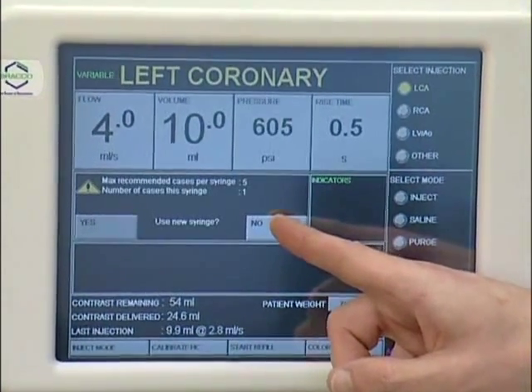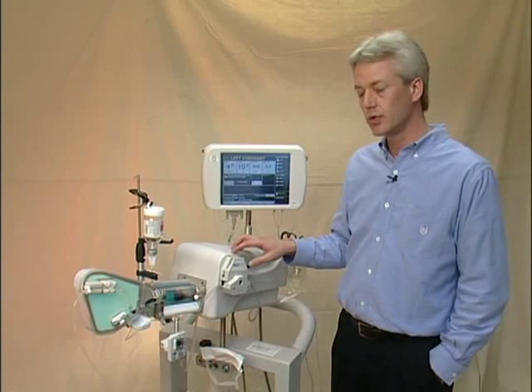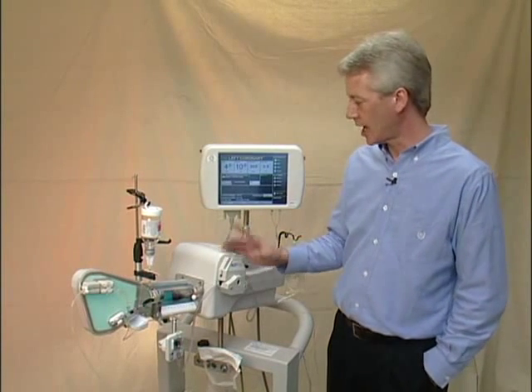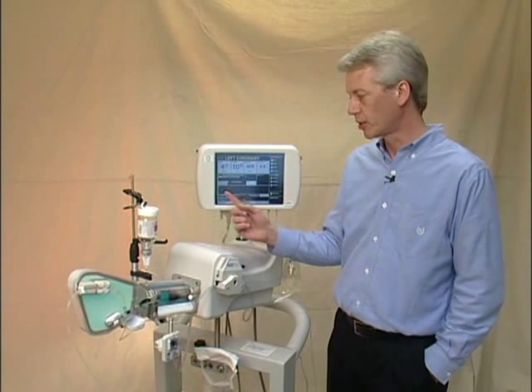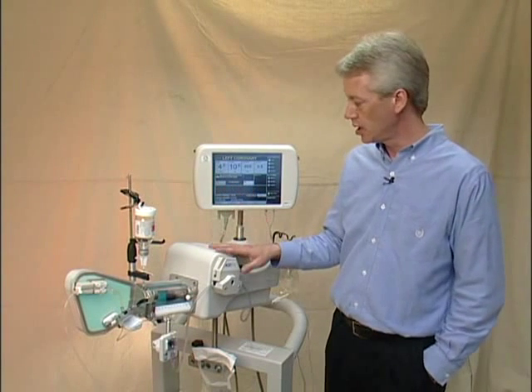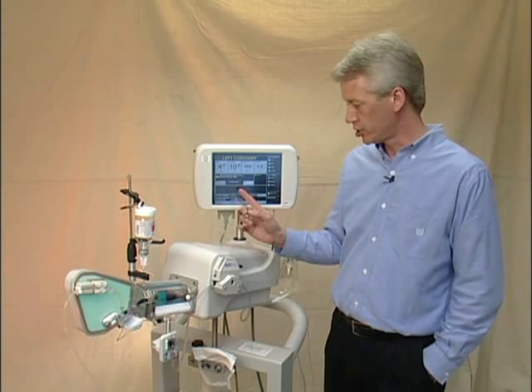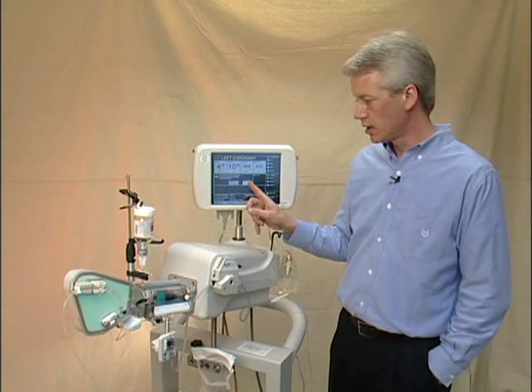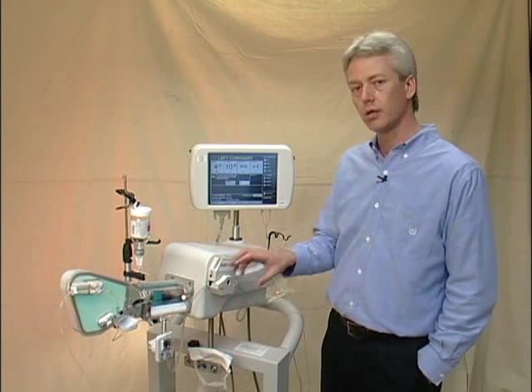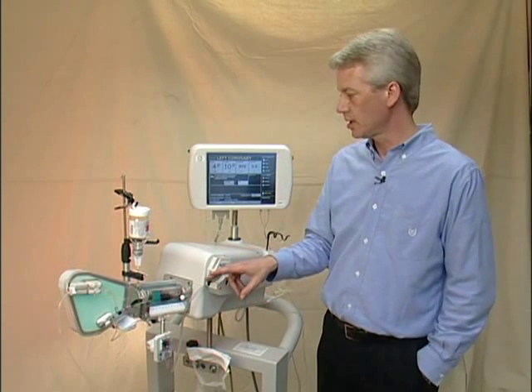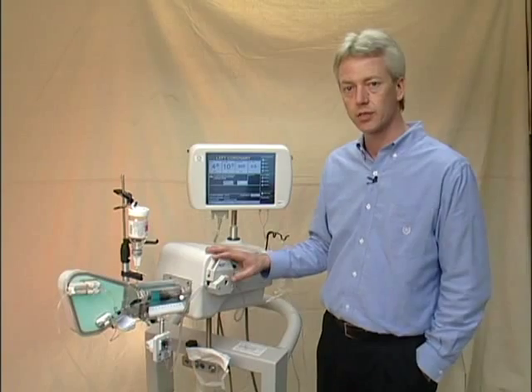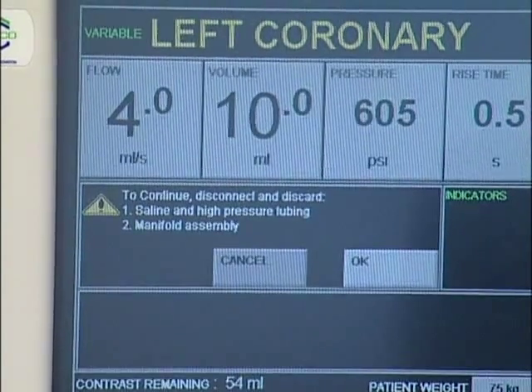We'll choose no. It tells me that the maximum recommended uses for the syringe is 5, and I've used this for 1 time. It'll prompt me to use a new syringe. If I haven't used it 5 times, I will choose no. And then the system prompts me to disconnect and discard the single-use components from the ACIST, and then walks me through the setup screens to hook up the next patient kit.